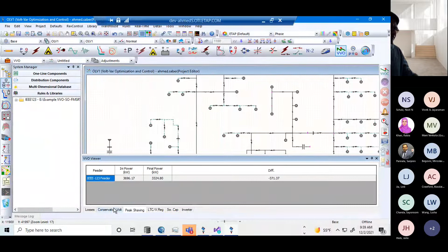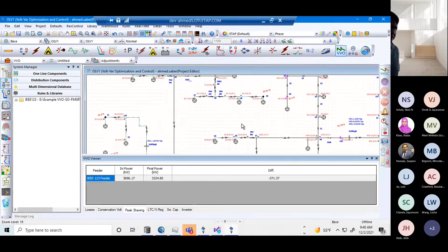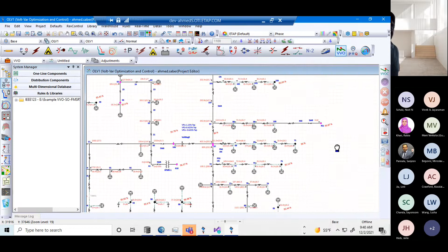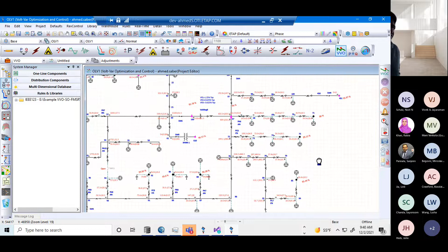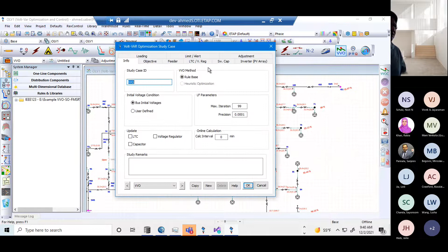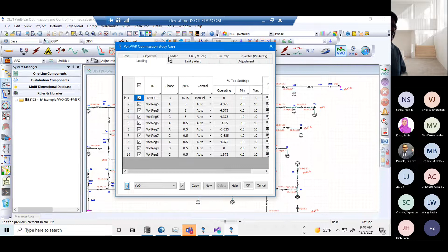So even if you go to lower voltage limits, you can see in the Volt-VAR optimization results, most of the end voltages will be around 95%. You see here 95.87, here 95.56. Maybe some other locations will be around 95. But some countries sometimes allow not only 95, maybe even around 90, and in that case you can reduce more power.